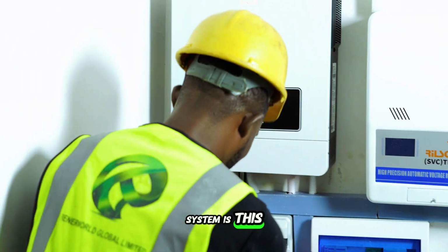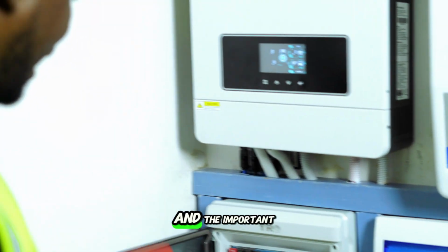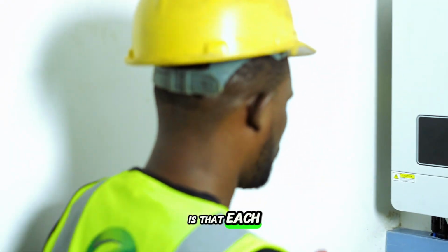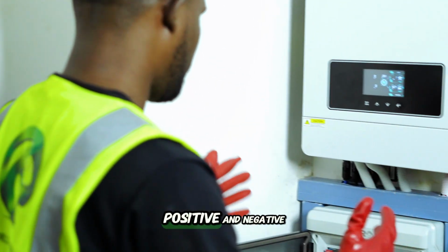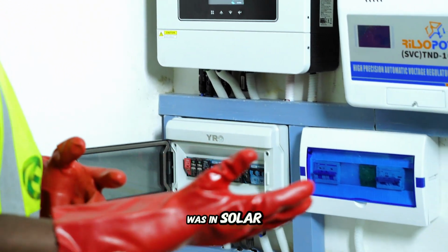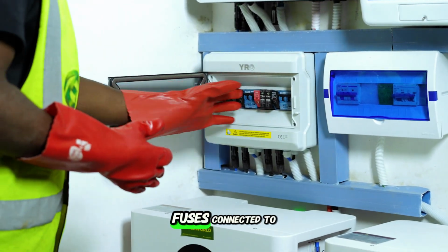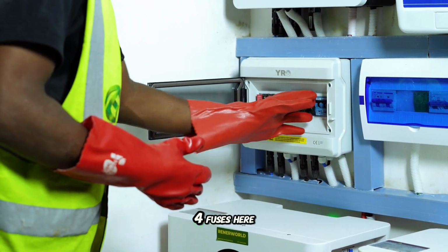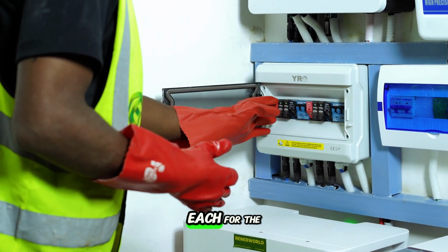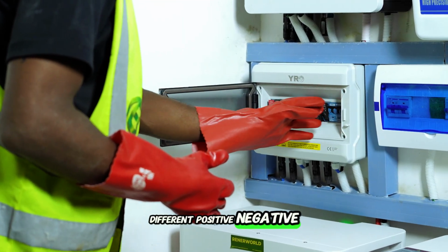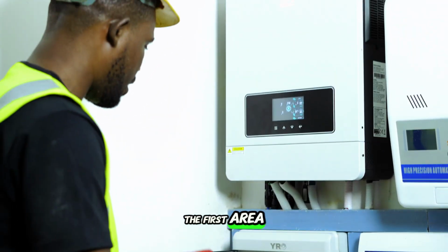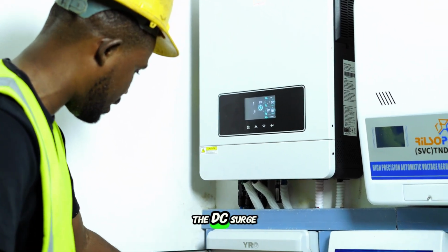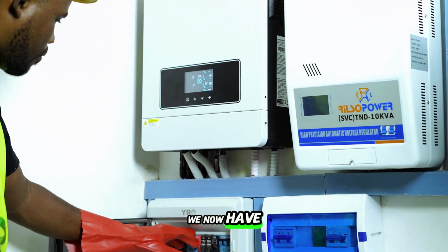One beautiful thing about this system is this combiner box. The important thing about it is that each of the positive and negative arms of the solar panel input has its own fuses connected to them. You can see about 4 fuses here, each for the different positive negative for the first array, and positive negative for the second array. We also have the DC surge protector before the DC breaker.